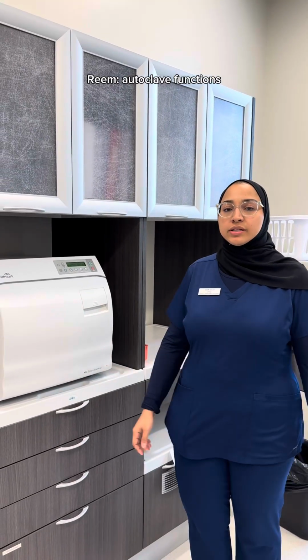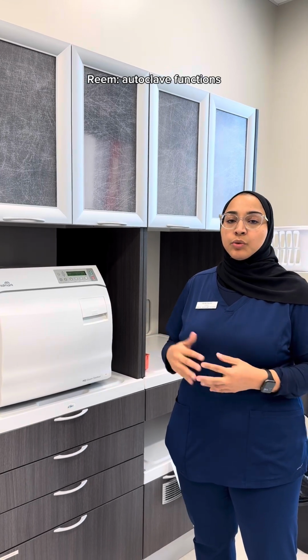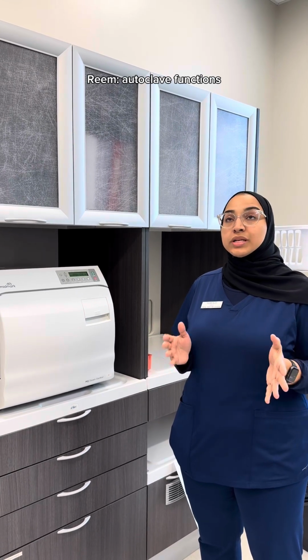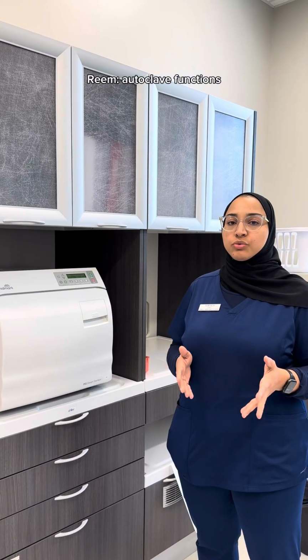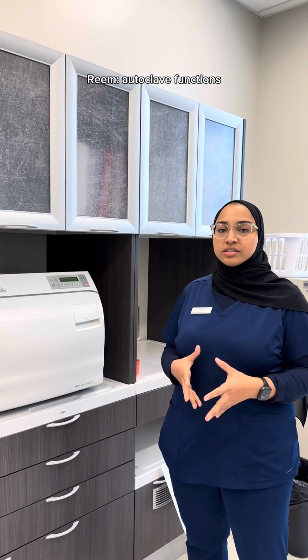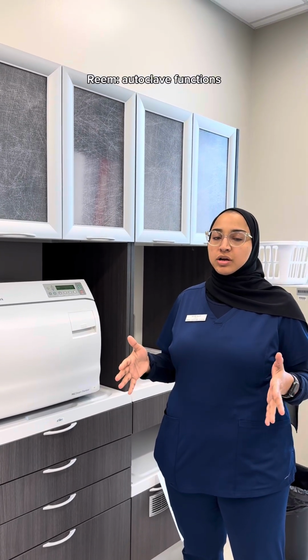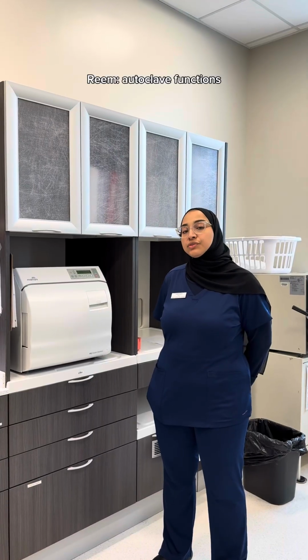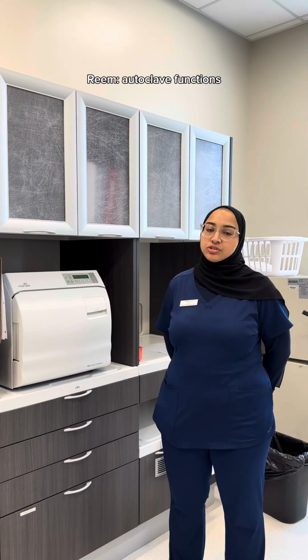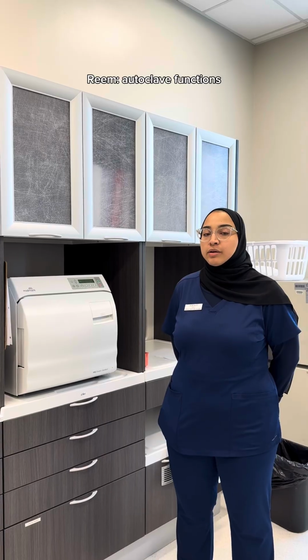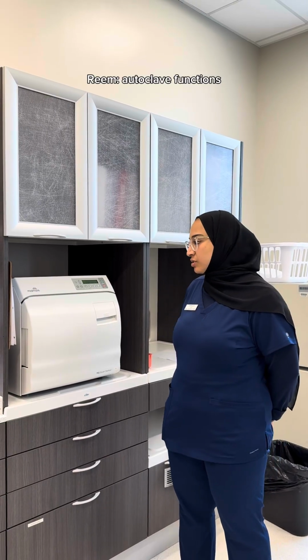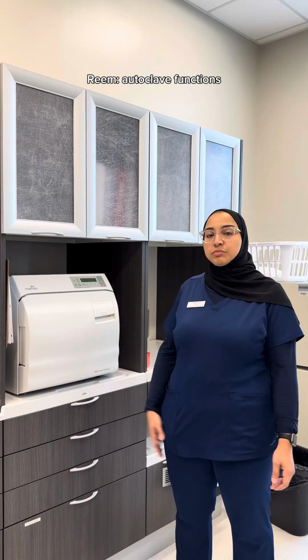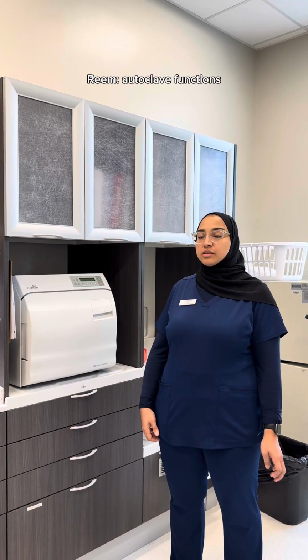After starting the unit, the heat up cycle starts and it starts building the steam in the chamber and the temperature as well. And once the temperature reaches between 250 to 273 degrees Fahrenheit, it holds the temperature and the sterilization cycle begins. After 30 minutes, the depressurization cycle starts, which will release the steam in the chamber and decreases the temperature and the pressure inside the chamber.